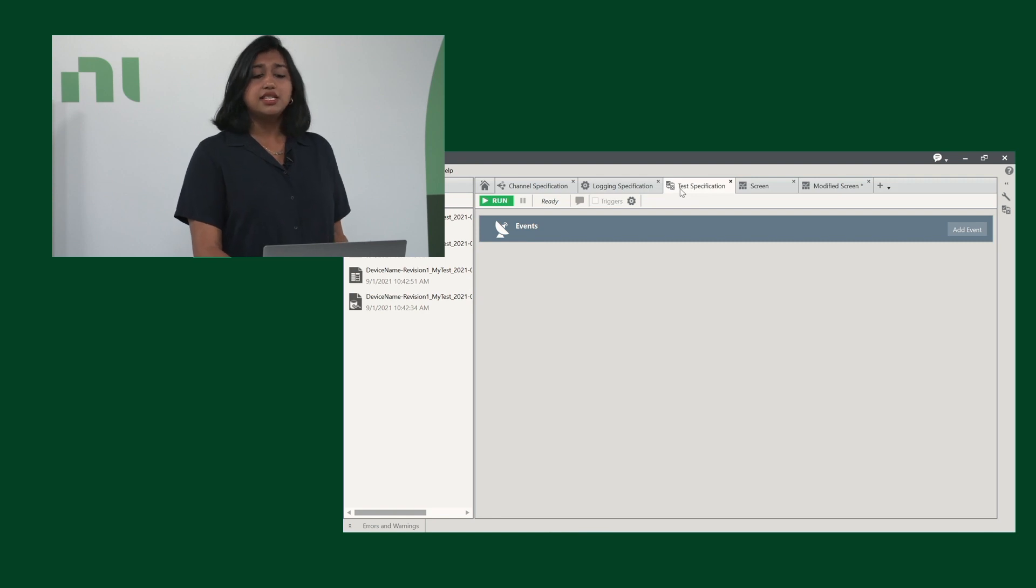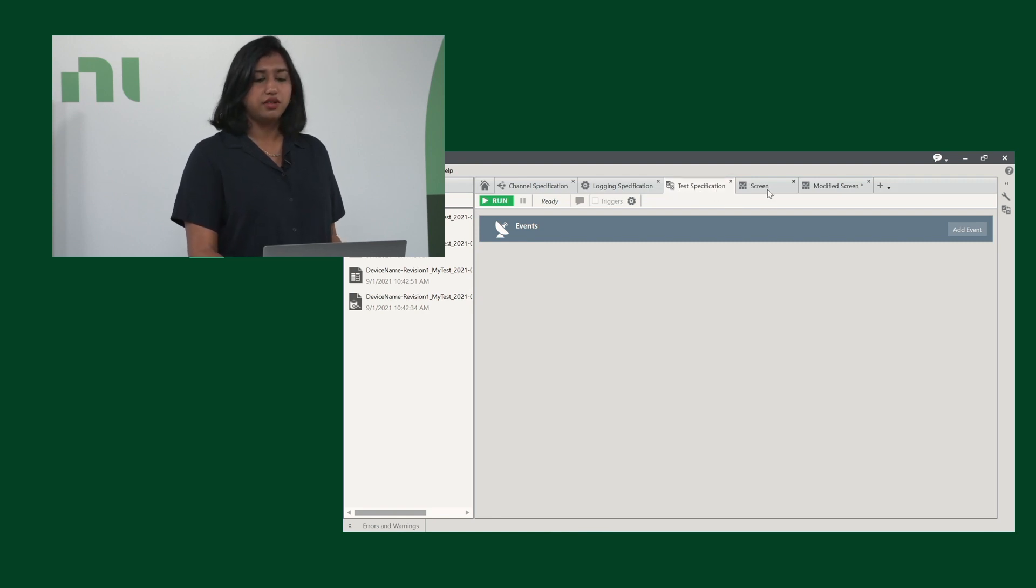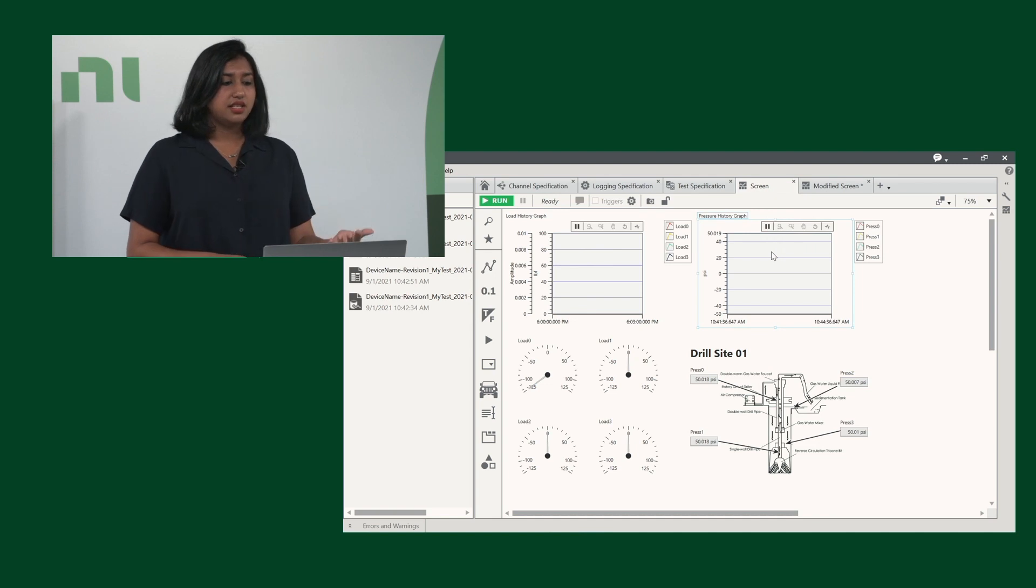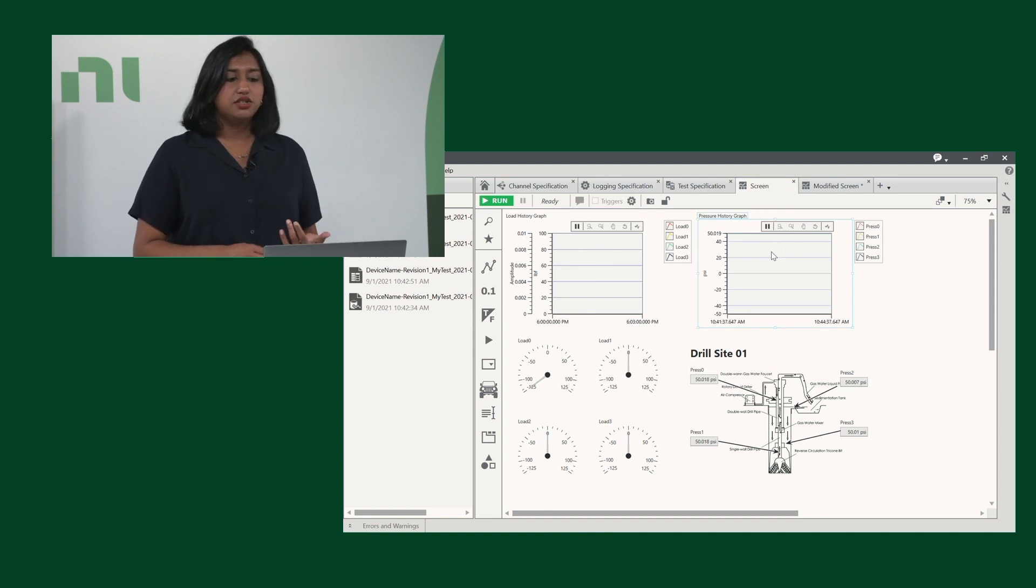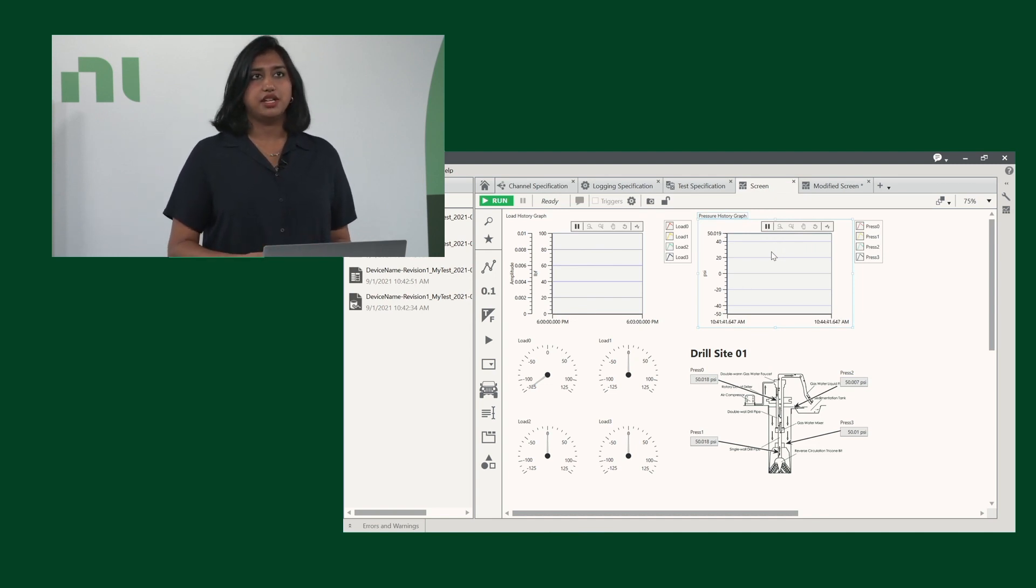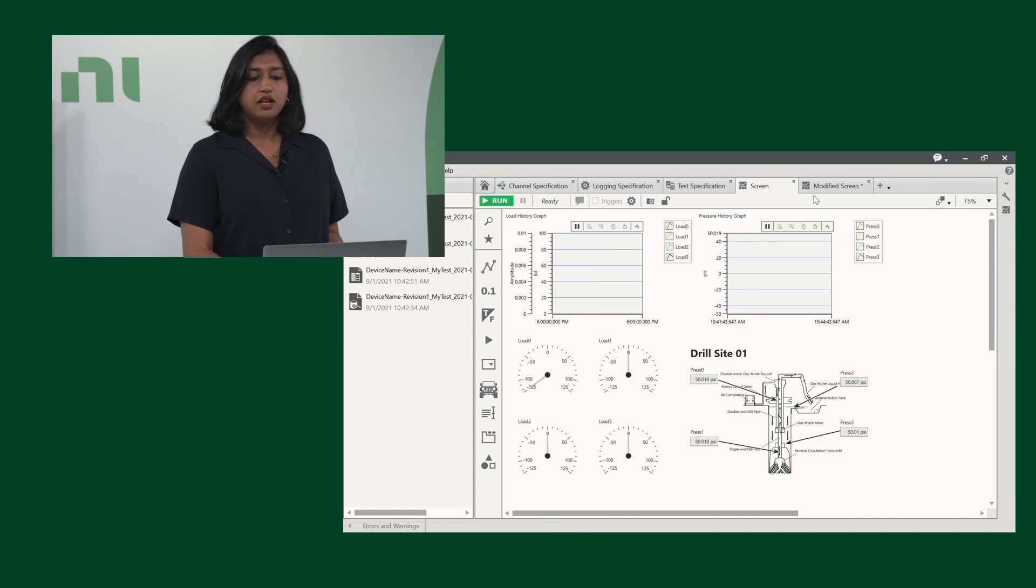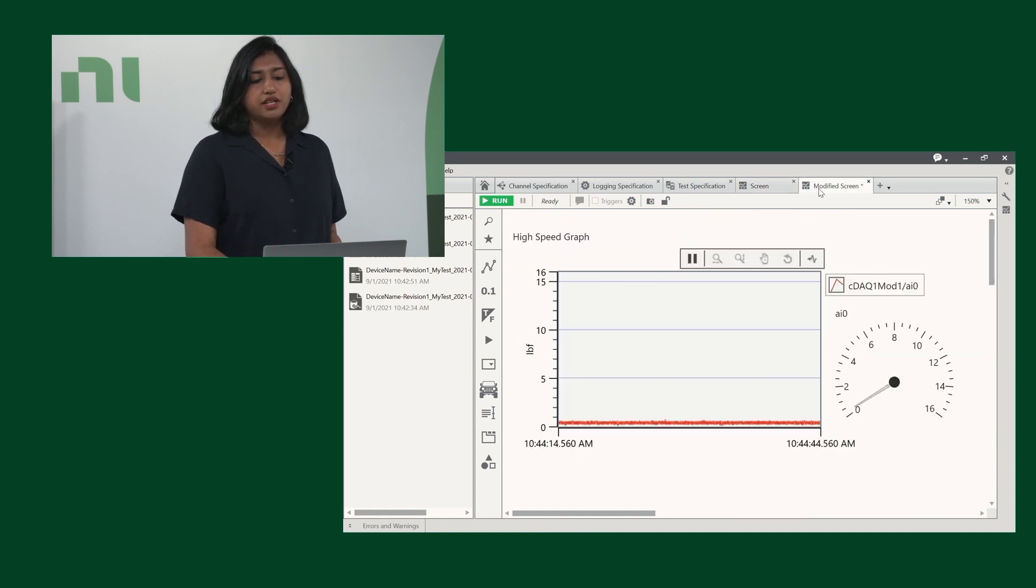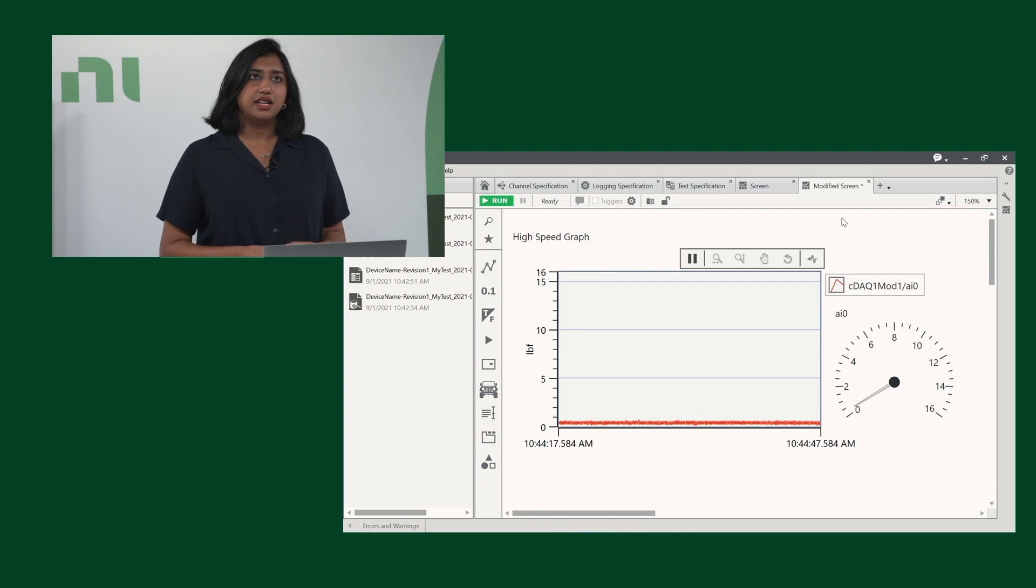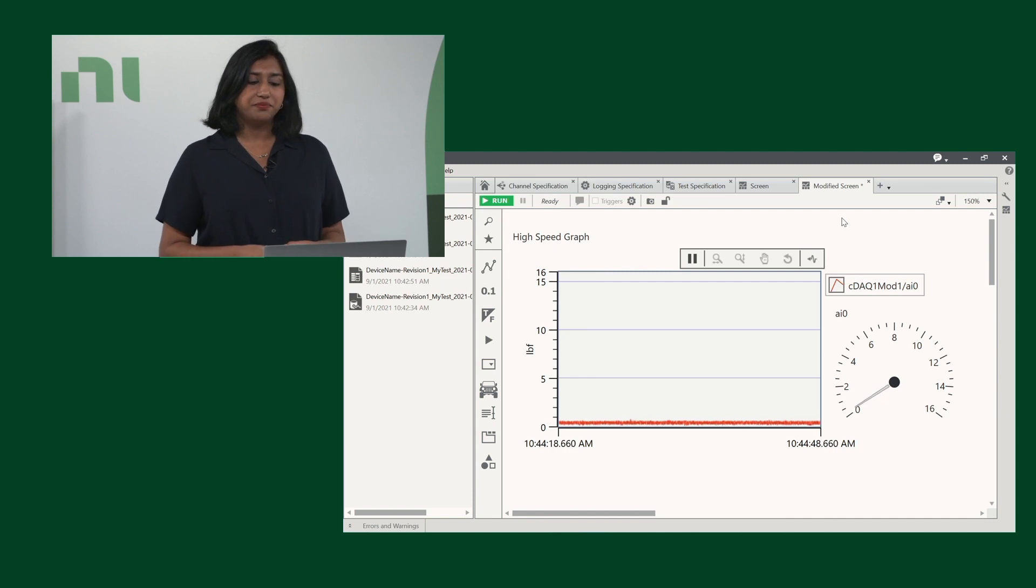And lastly, the default screen that we have available for this template is this. It has loads history graph, pressure history graph, and various other things to modify for your needs. The modified screen here is showing a high-speed graph so we can see the data in real time.